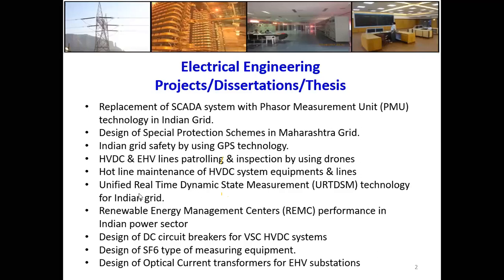Then we have Unified Real-Time Dynamic State Measurement, or URTDSM technology, for the Indian grid. The first phase of this is already implemented. Power Grid has installed the URTDSM system at major substations, at 400 kV and 765 kV levels, including some substations in Maharashtra. At SLDC we also have this URTDSM system. That was the first phase.